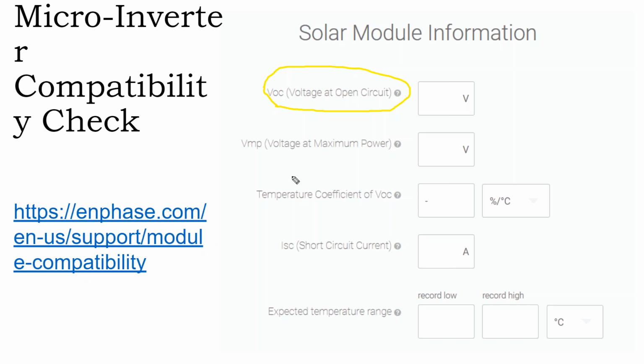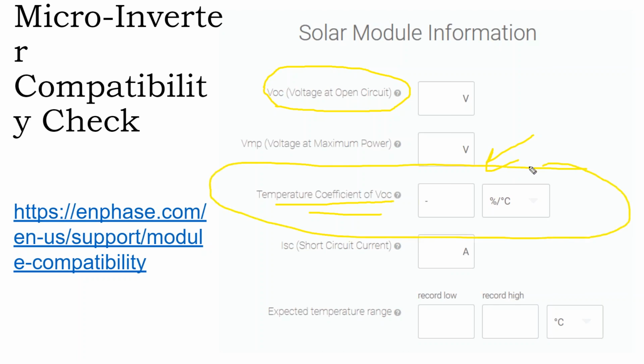When you're doing the voltage checks for compatibility, remember that the inverter's voltage rating is under a laboratory standard test condition. In old school solar, we would look up on the spec sheet, grab its temperature coefficient, and go and find the record lows and record highs. Here, we're just plugging in the temperature coefficient, and Enphase is going to do a rough check. These temperature coefficients are general enough that in electric code you actually have a table that will, as long as you're using silicon panels, allow you to use the table to check your voltage range rather than the individual panel itself, because they're that close together.